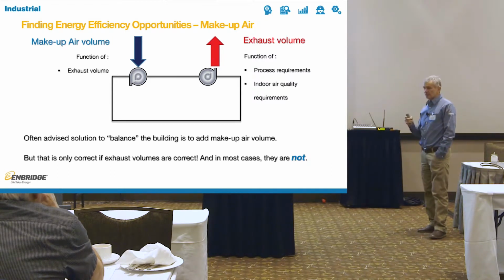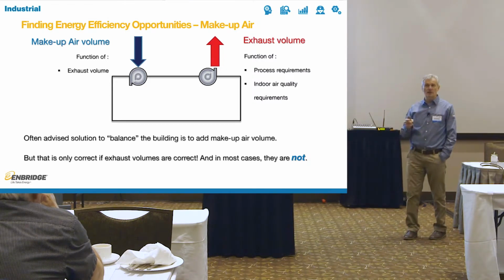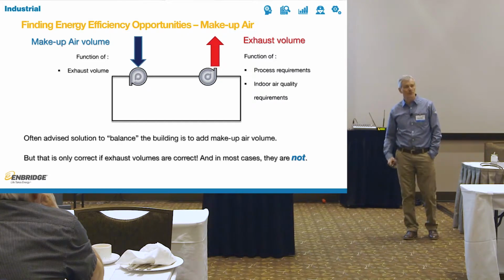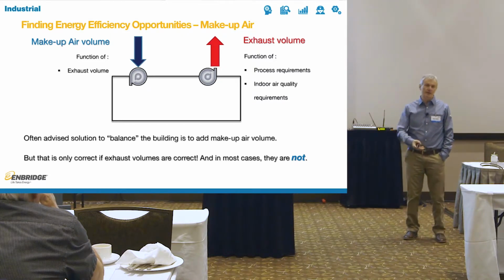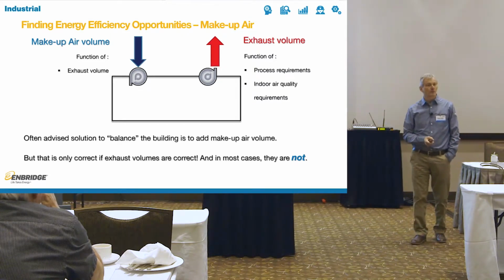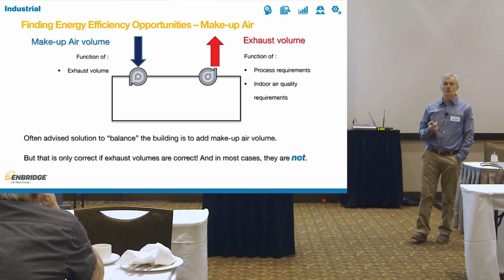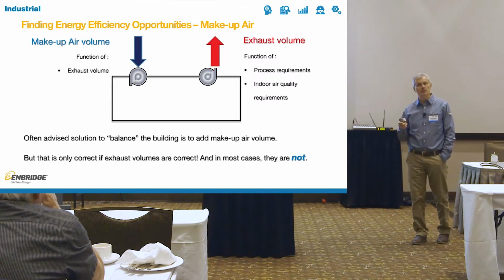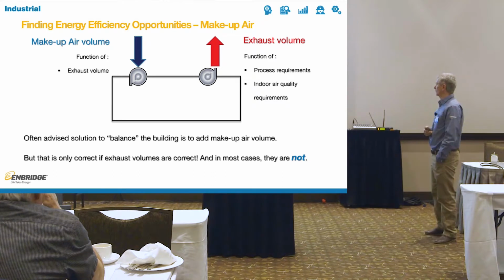And what often happens if you have an unbalanced building, with a lot of infiltration that closes the door behind you, is you call somebody and they say, yeah, you need more makeup air. Yeah, okay, that's all good. But how much does it cost you to put in another makeup air unit? How much does it cost you to run a makeup air unit? Well, we'll discover that a little later on.